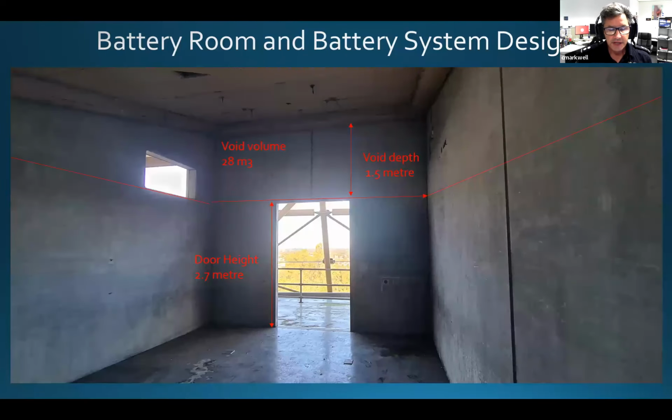And this is from the rear of the compartment looking out towards the double door entry point. And again, highlights what I'll call the receptive void in the top part of the compartment. So in terms of ventilation points, the upper outflow ducts were the first points, but again, protected by fusible dampers, which did activate and seal off the compartment. So therefore, the next available lowest ventilation point became the top of the doorways.